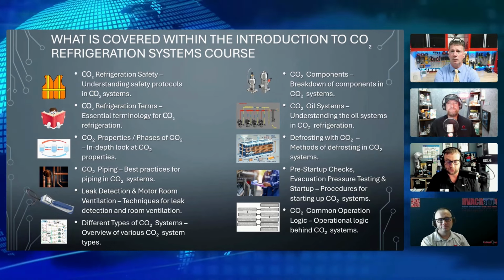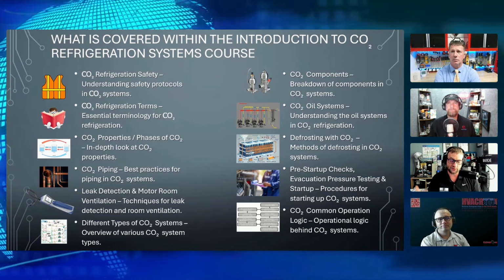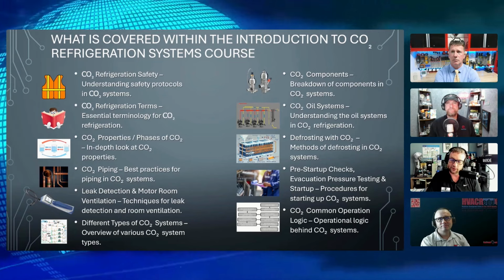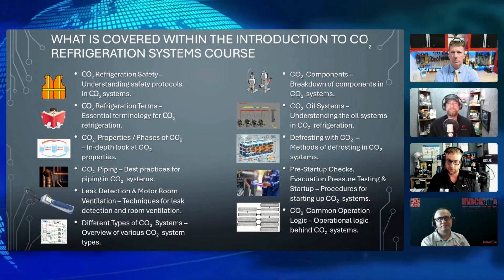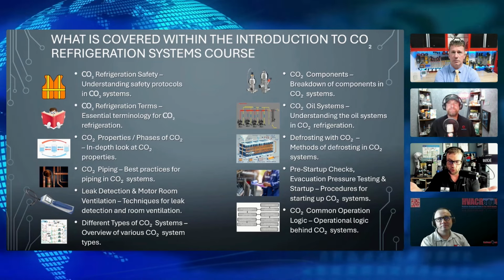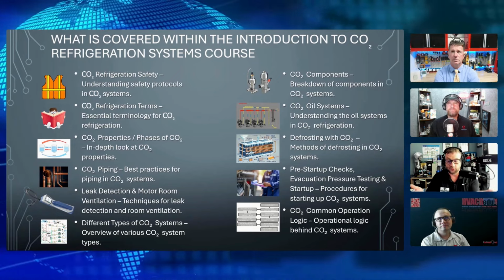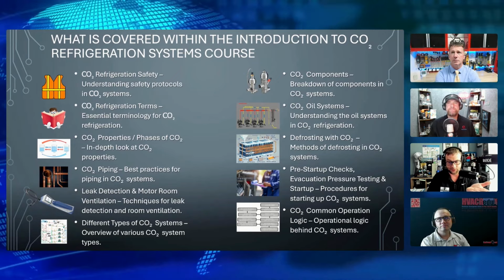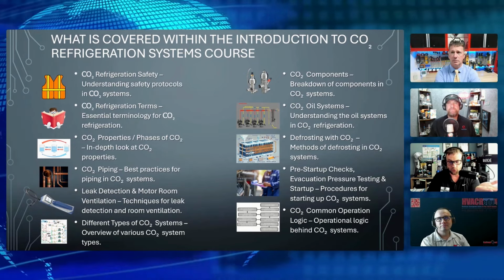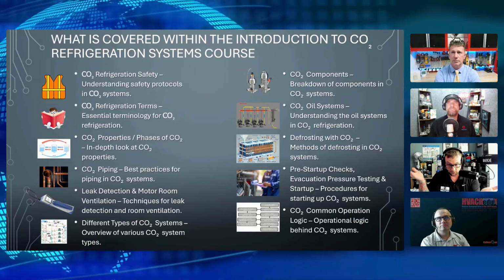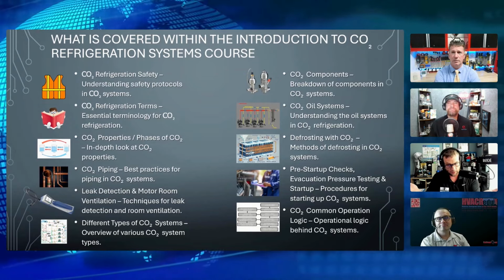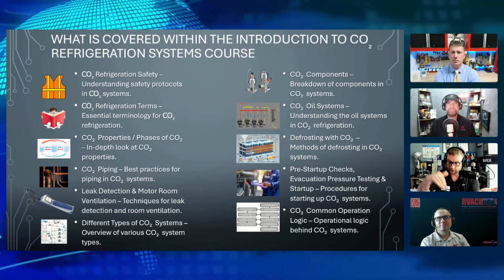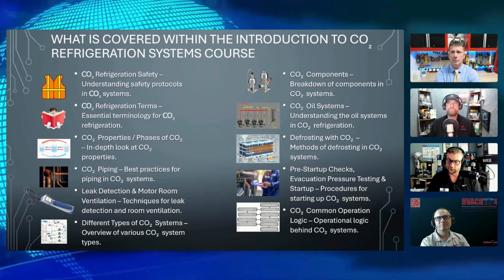Well, it's not a booster system. You have to remember the discharge of the low temp is discharging directly into the suction of the medium temp. So without the medium temp, I have no low temp. Exactly, which kind of stinks sometimes, because if you have a whole bunch of failures on the medium temp, you don't just lose the medium temp, you lose the capacity of the low temp as well. Correct, because there are no compressors to take the discharge of the low temp in there, right?